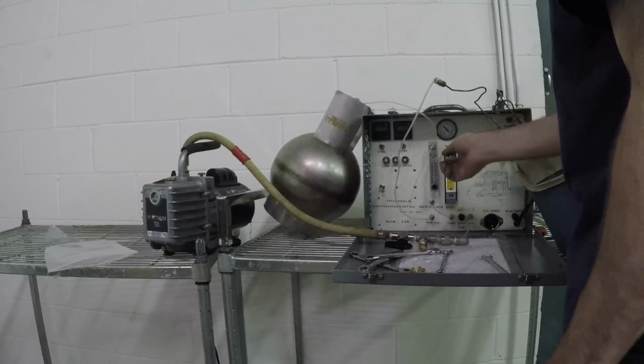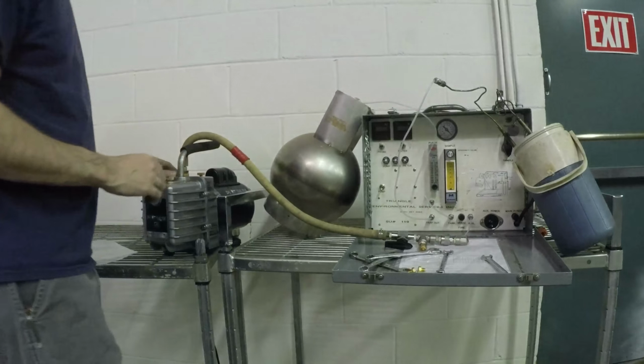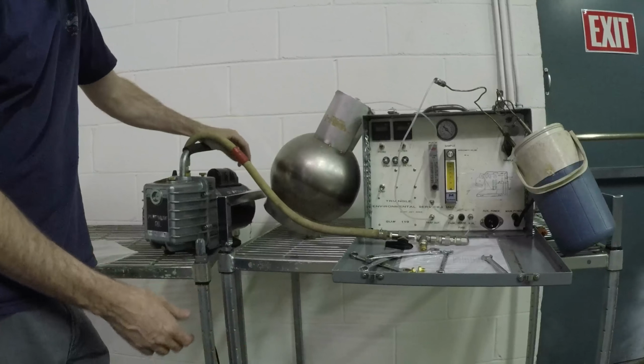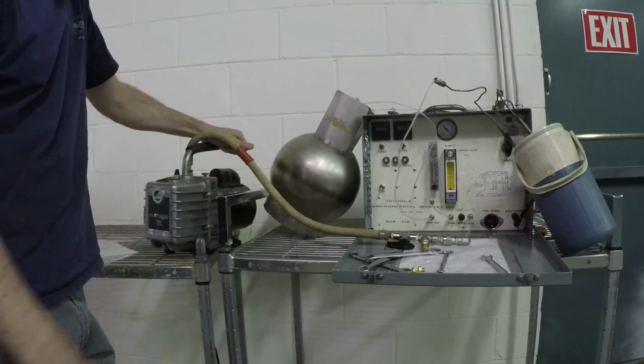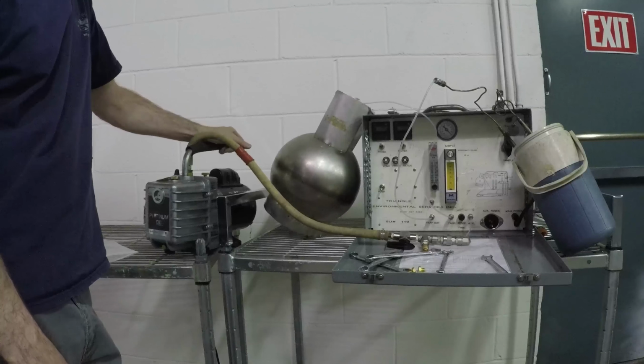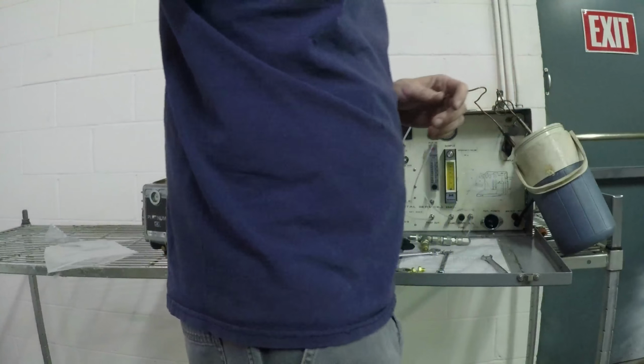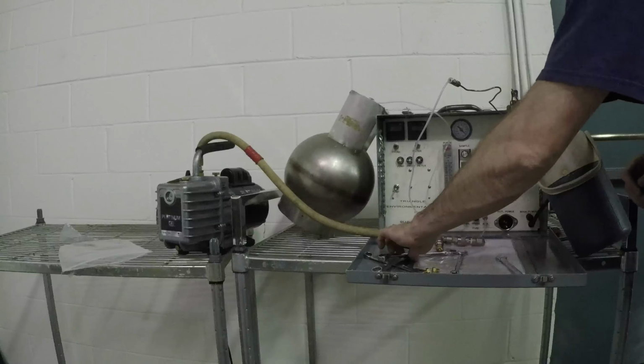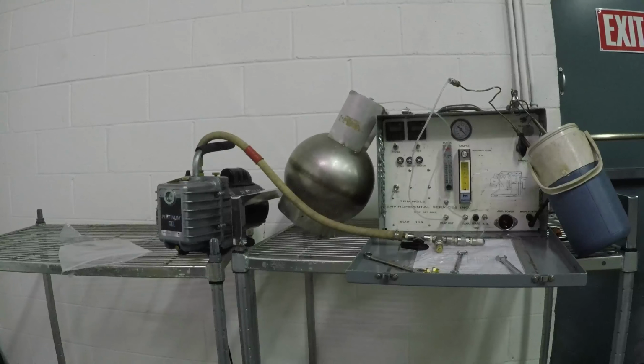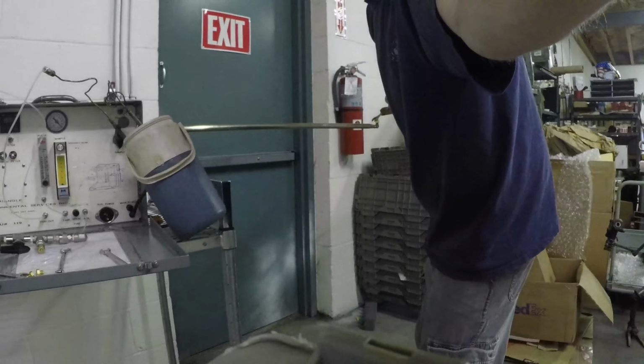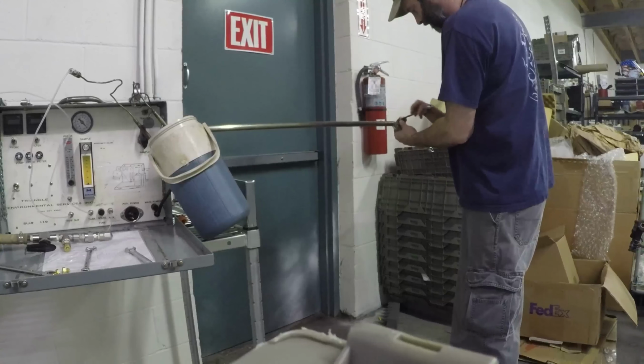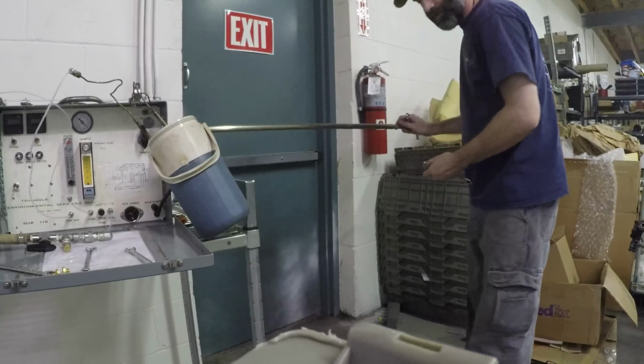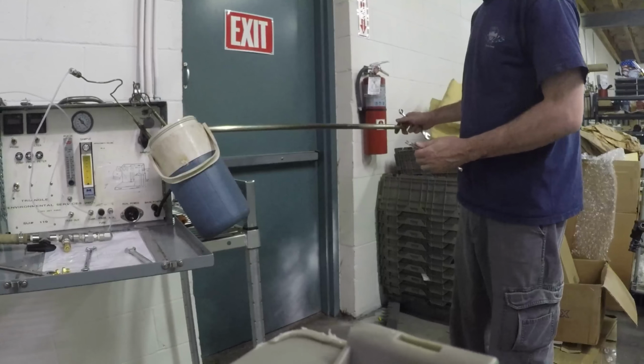Sample valve is open, turn your pump on, pull it down to a hard vacuum. Again, as long as it holds to its acceptable parameters, you are now good to sample. So what you do, down here to the end of the probe, hold it off. Attaches to your source. This will go into your stack, source, whatever it is that you happen to be testing.